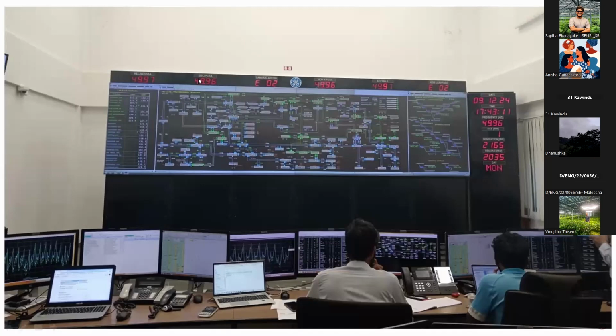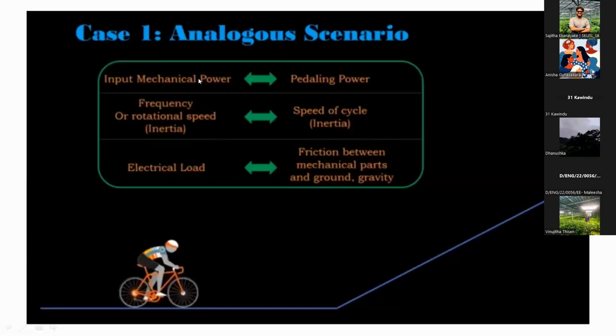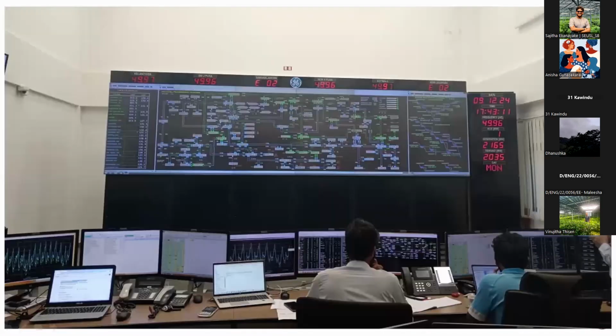This is what they use to know whether they have balanced it. They're not going to measure the demand directly and check whether they've balanced it - they just observe the frequency, only the frequency. By observing the frequency, they know what has happened. If frequency is around 50 hertz, that means they have balanced it. If frequency is dropping, they know the demand is higher than the generation. If frequency keeps increasing, they know the generation is higher than the demand. That is how they identify it.